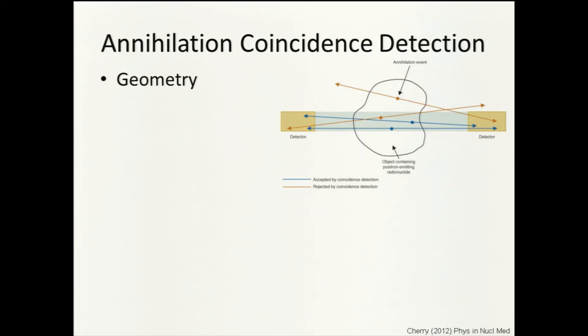This brings us to annihilation coincidence detection. Our abstract rat in cross-section is filled with a radioactive tracer whose radionuclei decay, emitting positrons that annihilate, producing outgoing photons on straight lines back-to-back. If we place detectors outside the subject and require that we only see signals arriving at the same time — in coincidence — then an annihilation event inside the subject will trigger two detectors simultaneously. An event outside the subject will hit one detector but not the other. The electronics require events to occur within a few nanoseconds of each other.